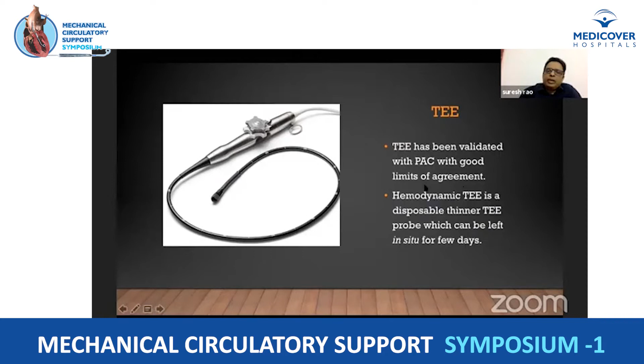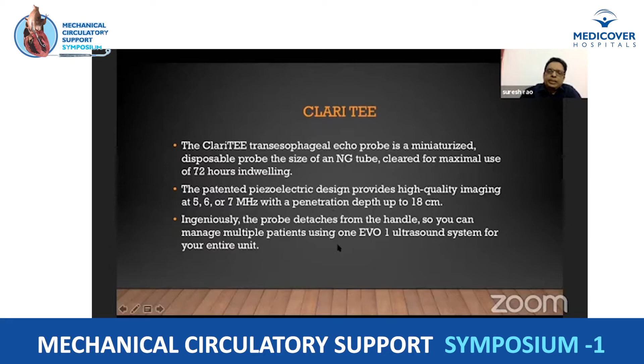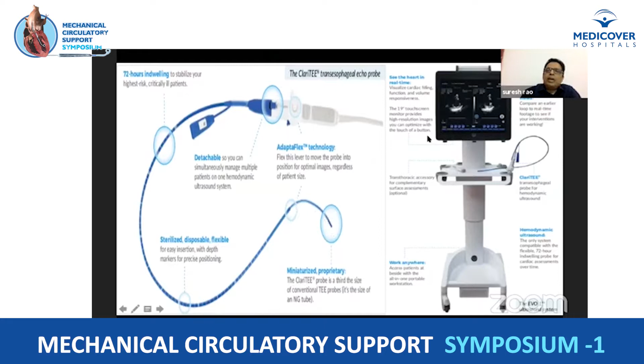Basically, it is a ClariTEE, and it has a disposable probe which is the size of a nasogastric tube. It has a patented piezoelectric design and gives around 7 megahertz of ultrasound frequency with a penetration of around 18 centimeter. You can detach the probe from the main machine, so that if you have one machine, you can use it in multiple patients with multiple disposable probes. So this is the ClariTEE. The blue one is the disposable component, and you can antiflex or retroflex. This has a 2D probe, and this is the console where you can have the images.